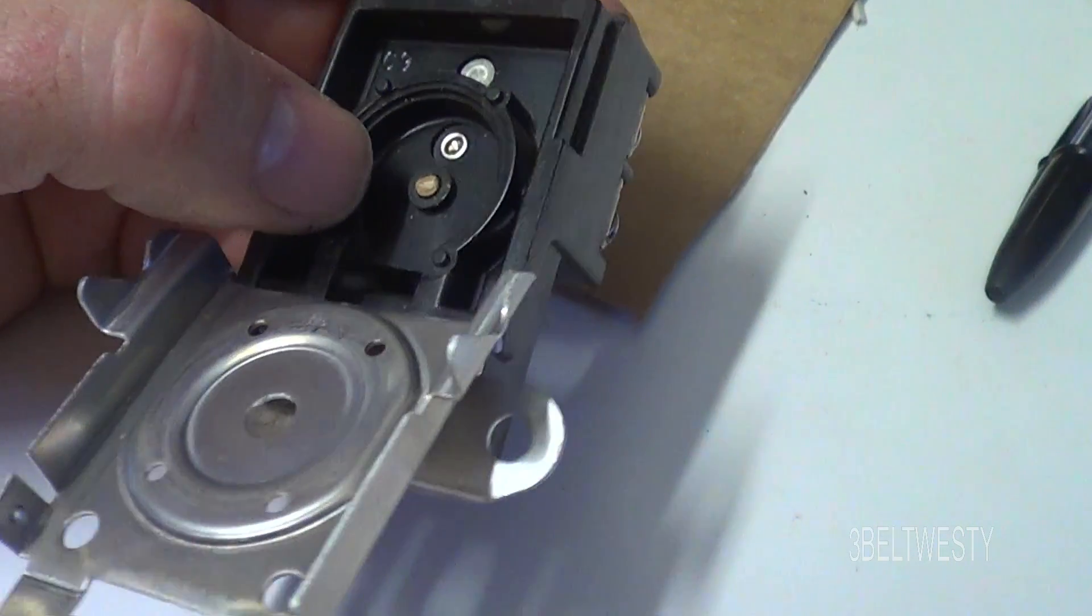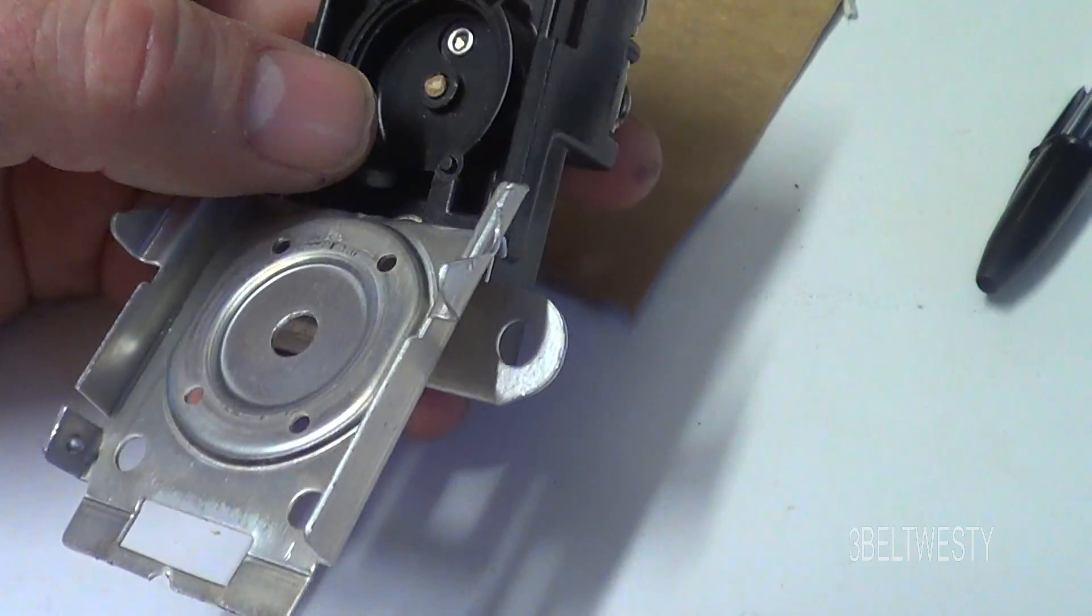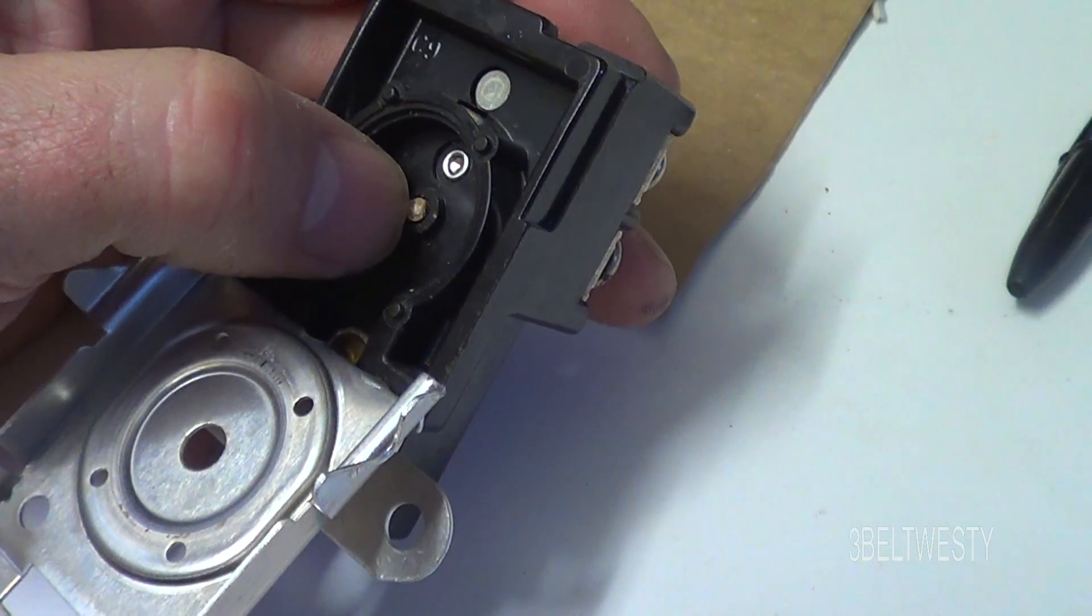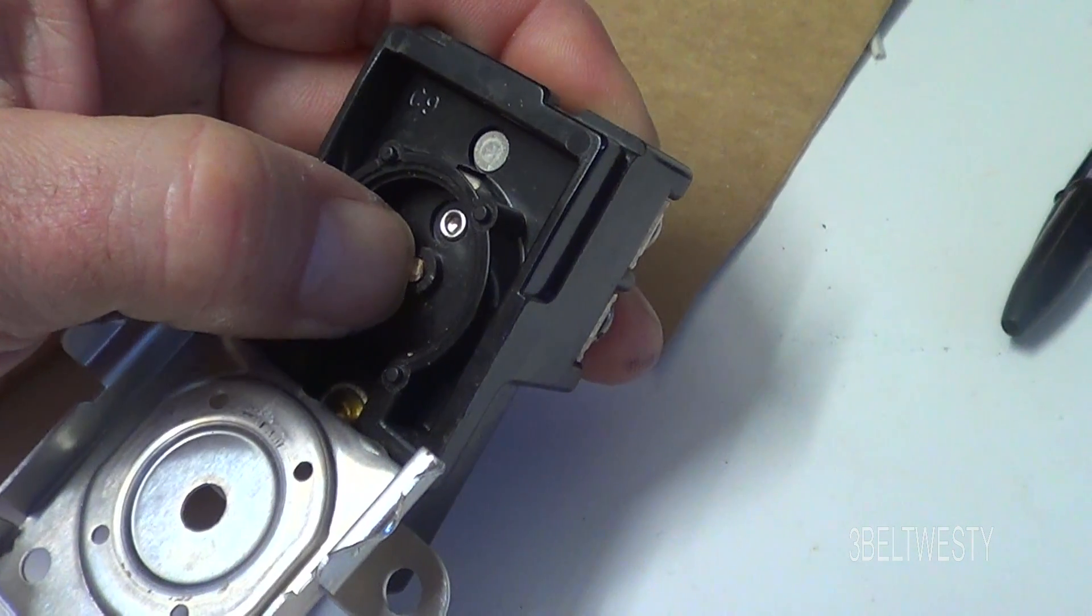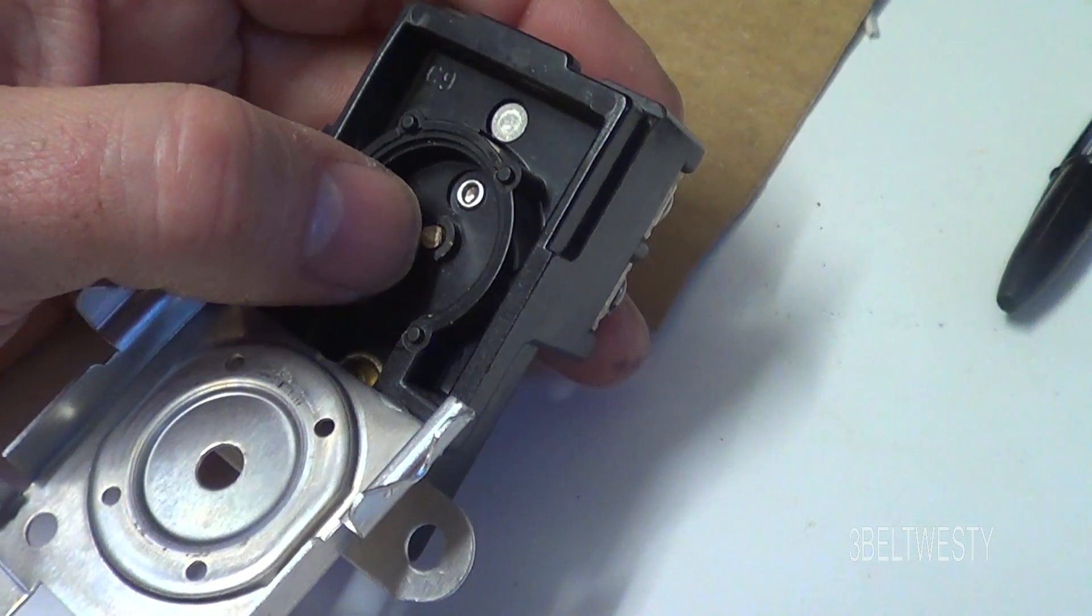But what happened on this one, which is only six months old, they probably used the wrong type of plastic here. And so this was completely seized up on its bore. And so that's why it was either intermittent or basically not running.